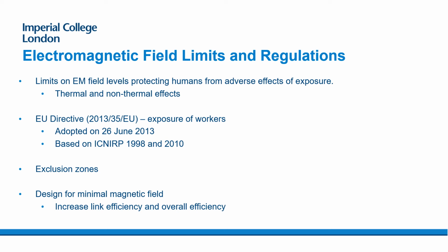It may also mean that you operate the design in a specific way. You might need to make sure your impedance levels, your reflected impedance levels, and your coil designs are such that you end up with, perhaps, a design for a minimal magnetic field, in other words, keeping the currents controlled in the coils and therefore not creating an excess magnetic field, in order to improve the safety of the system.